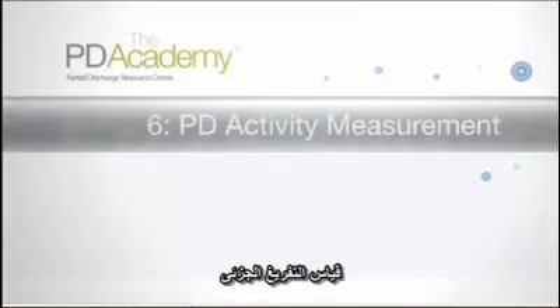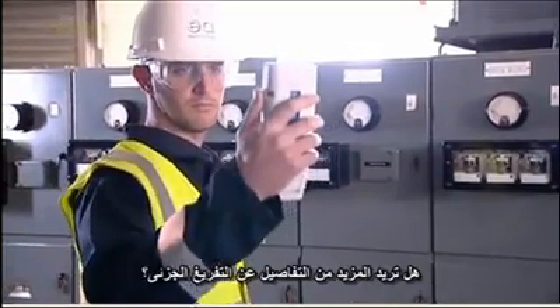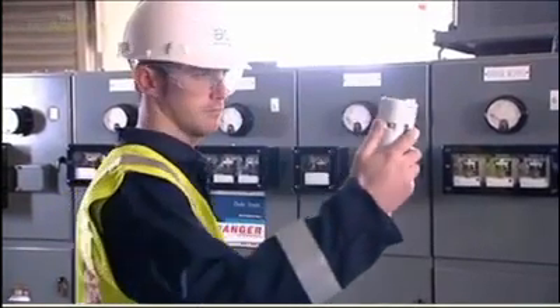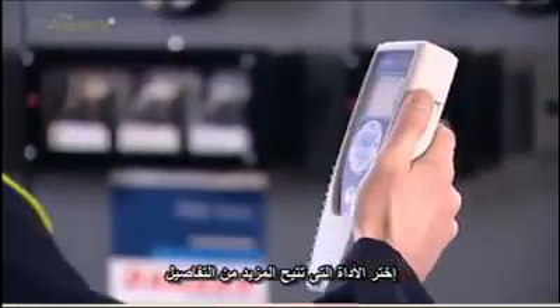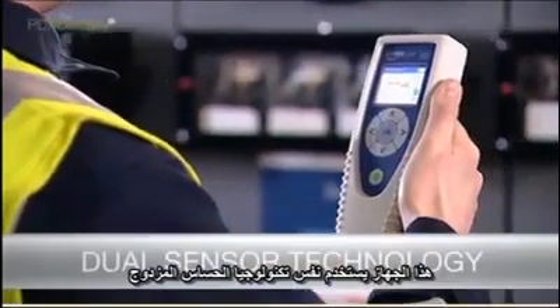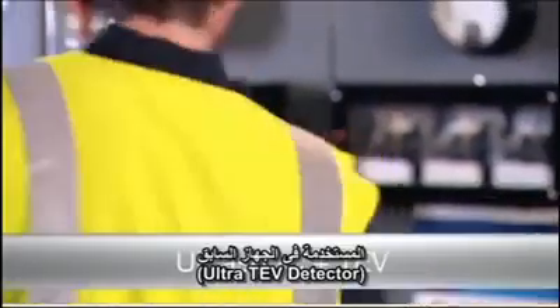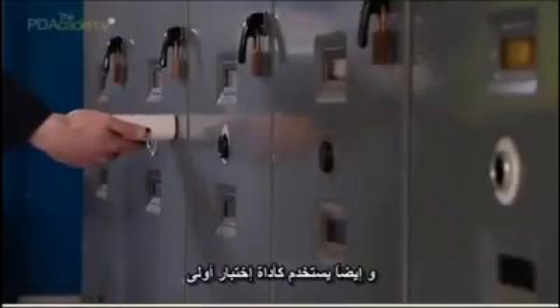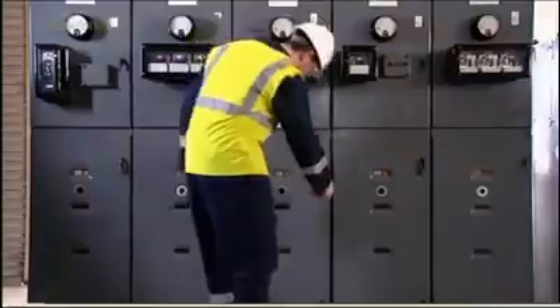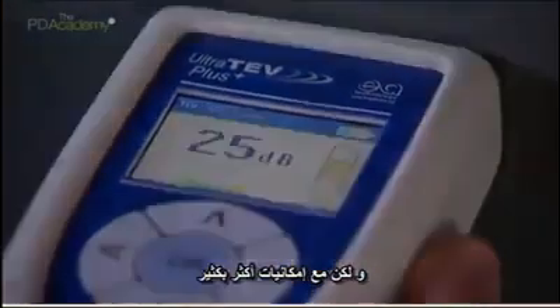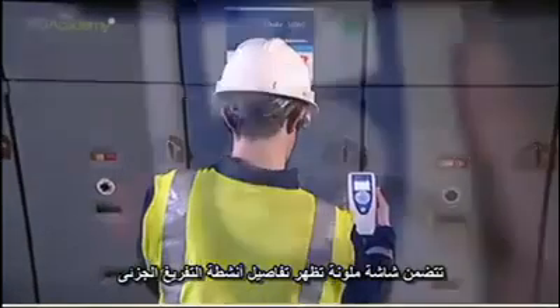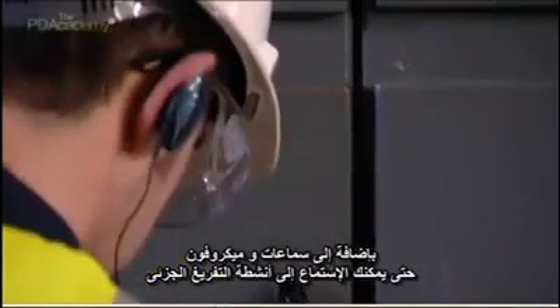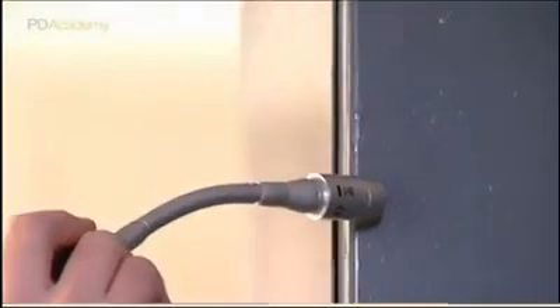PD activity measurement. Want more information about PD activity? Choose an instrument that provides greater detail. This type of instrument uses the same dual sensor technology as a simple traffic light detector, and it works just as well as a first-pass fault detector, but with a lot more features, including a color screen showing details of PD activity as numerical and graphical values, plus a set of headphones and a microphone so you can listen to PD activity as audible signals.